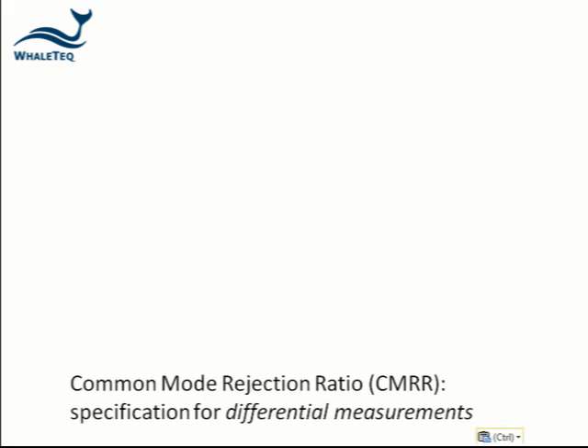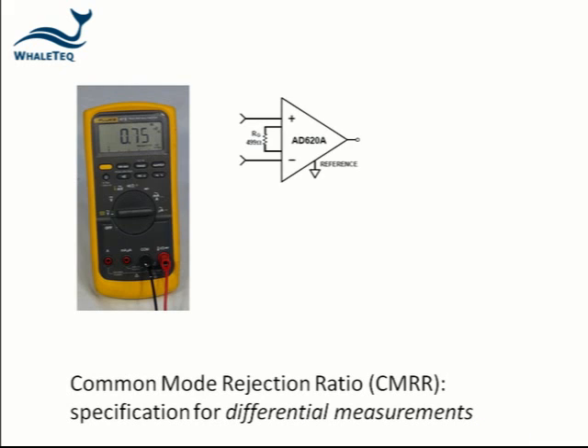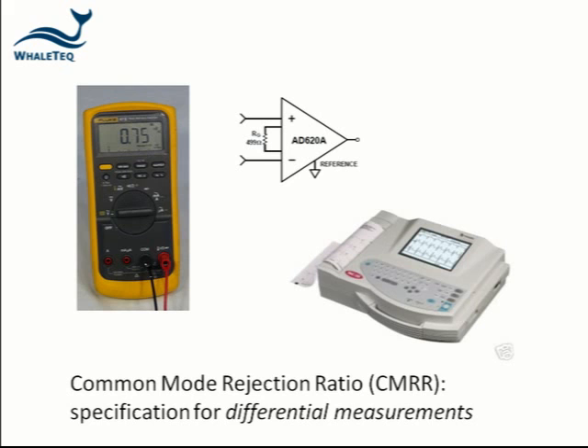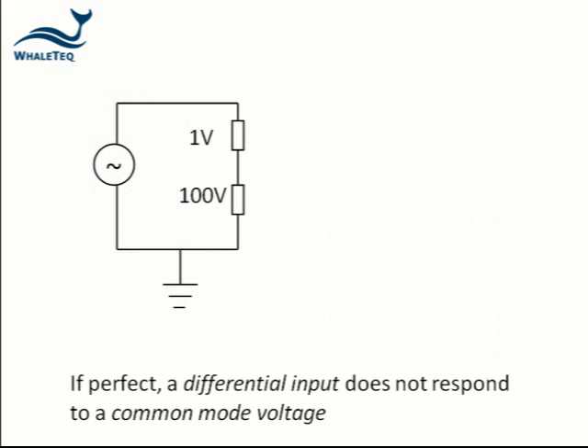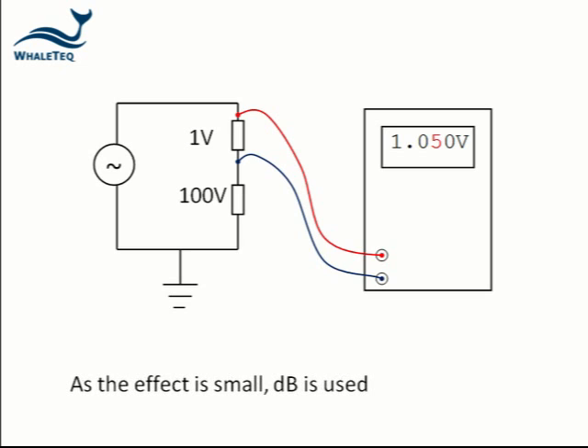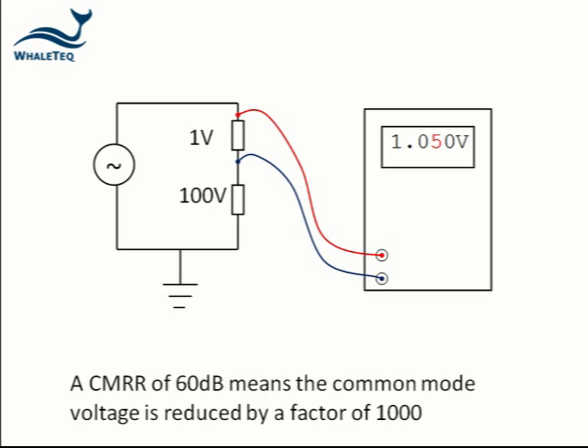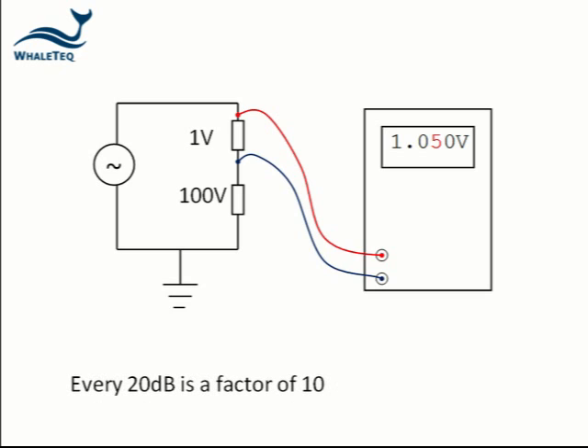Common mode rejection ratio is a typical specification for any equipment with a differential voltage measurement, including multimeters, differential amplifiers, and of course ECG equipment. In a perfect world, a differential input would not respond to any common mode voltage. In practice there is a small effect. Because the effect is small, the specification is normally declared in decibels or dB. A value of 60 dB means the common mode voltage is reduced by a factor of 1000. Every 20 dB is a factor of 10.